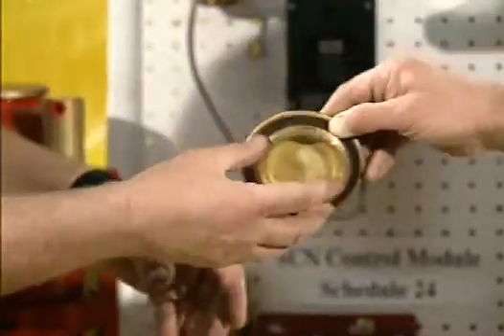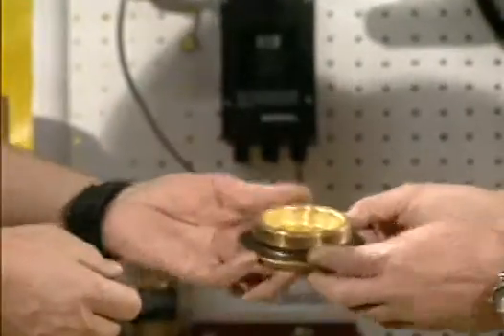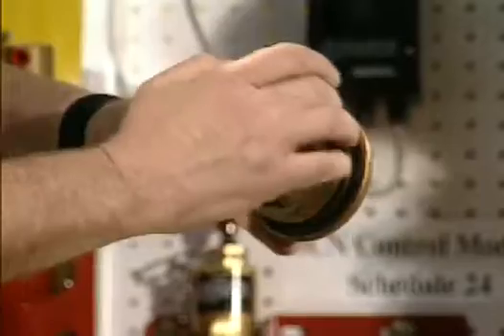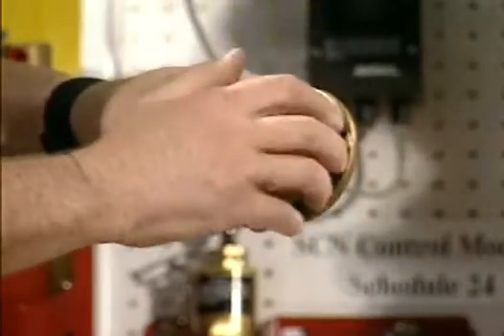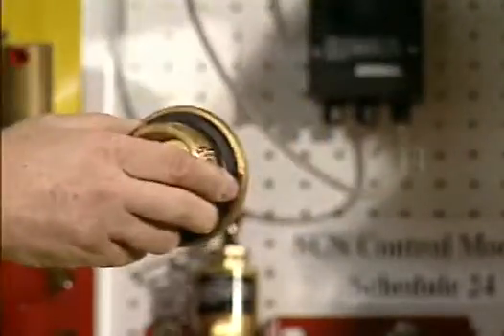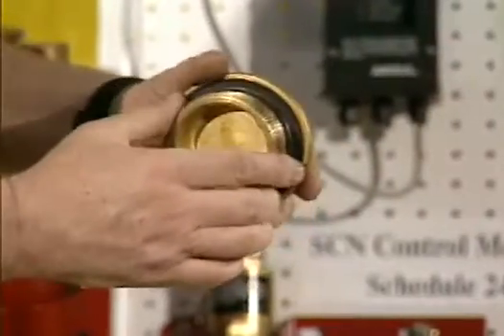Okay. So, we talked about the O-ring and the gasket on the bottom. This is what you were talking about? Right. These need to be kept greased. On a semi-annual inspection, this cap should be pulled, the chemicals should be checked from the top as well as the bottom, and these rings should be greased.